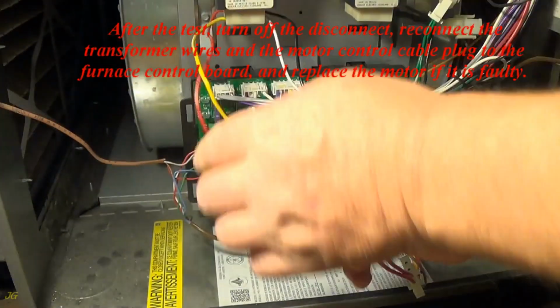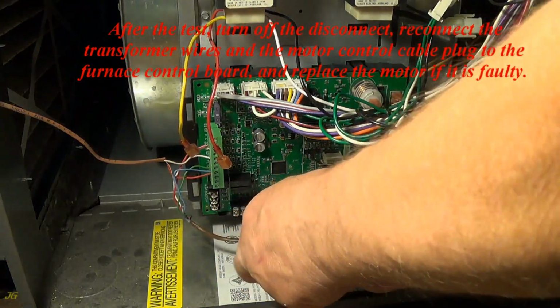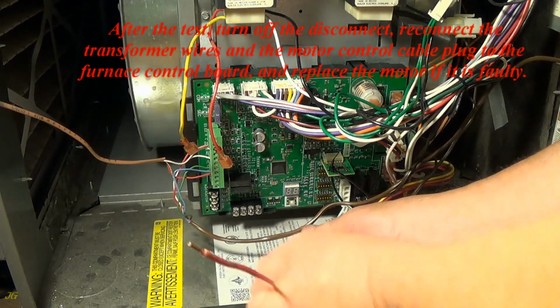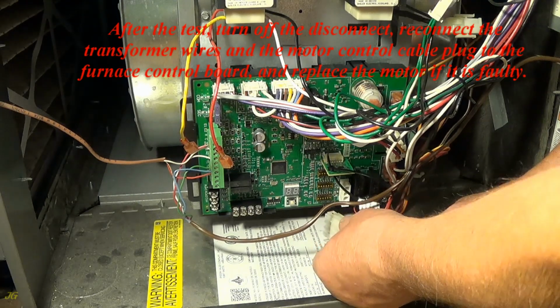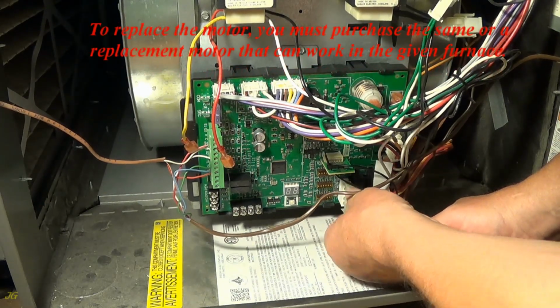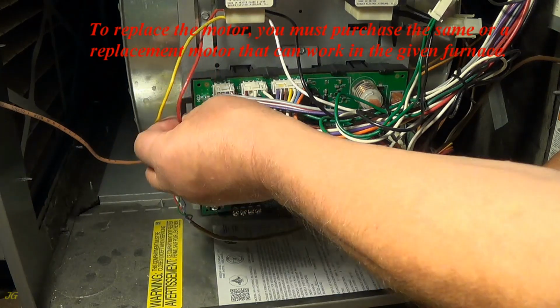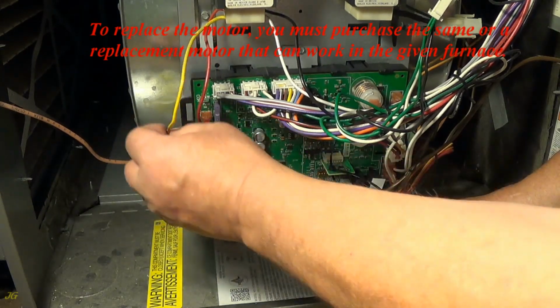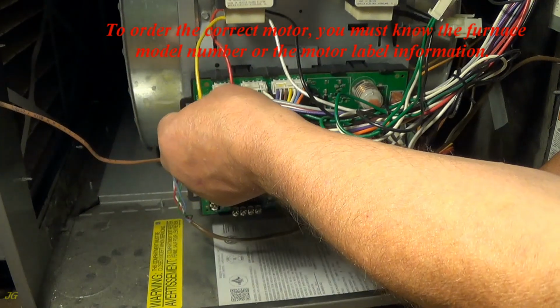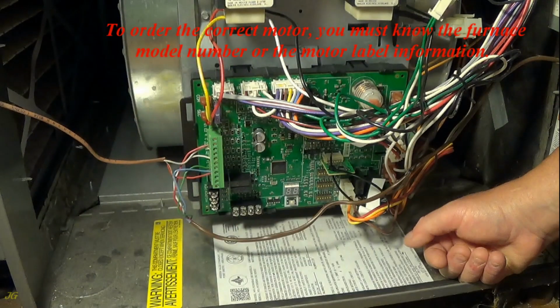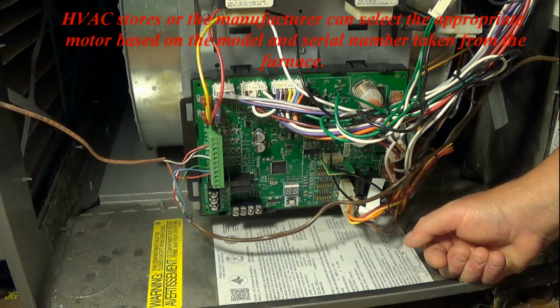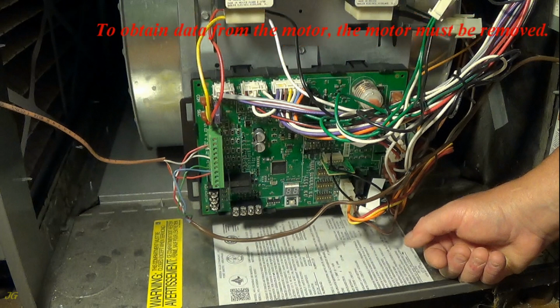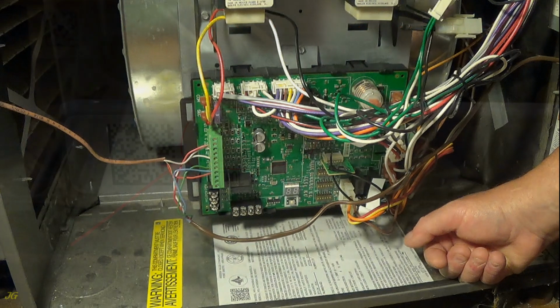After the test, turn off the disconnect, reconnect the transformer wires and the motor control cable plug to the furnace control board, and replace the motor if it is faulty. To replace the motor, you must purchase the same or a replacement motor that can work in the given furnace. To order the correct motor, you must know the furnace model number or the motor label information. HVAC stores or the manufacturer can select the appropriate motor based on the model and serial number taken from the furnace. To obtain data from the motor, it must be removed.